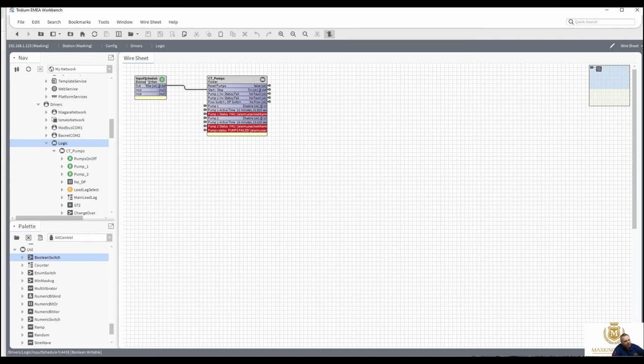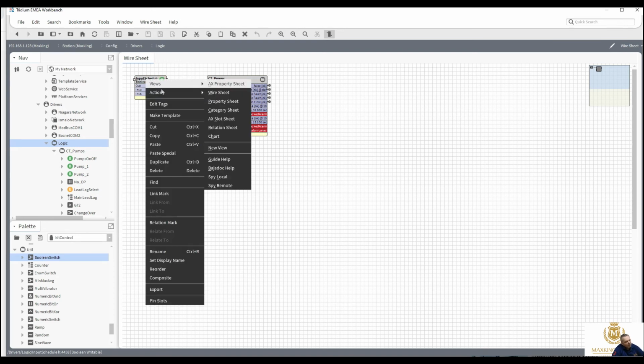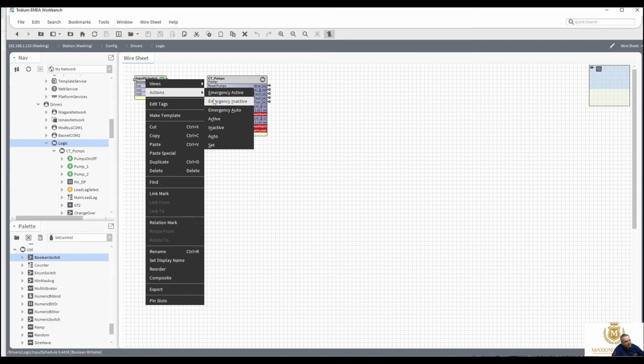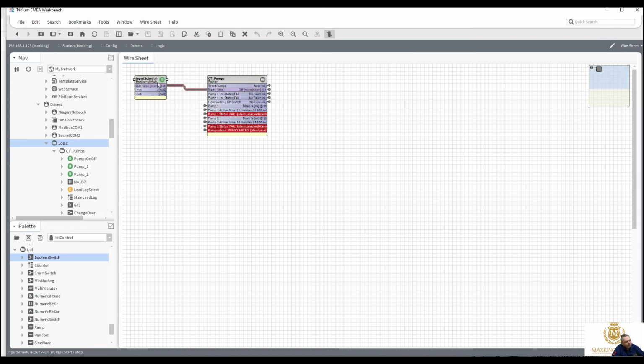I'm wondering whether we should do an automatic reset once the system is turned on and off. There won't be harm in doing that. So when you actually turn it back on, i.e. on a time clock, it just automatically sends a reset to reset anything that may be in fault, and if it's still in fault, it's going to go into fault. So yeah, let's do that.